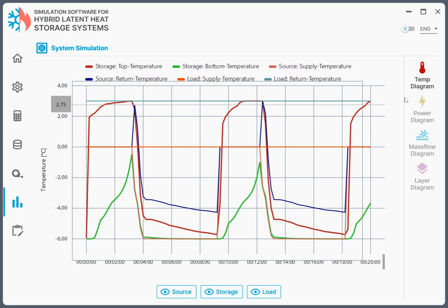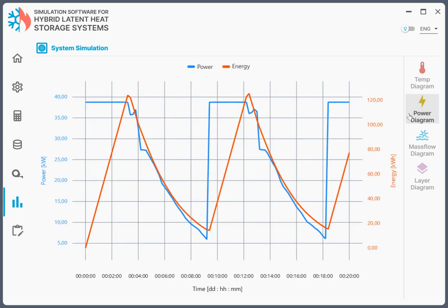You now see the behavior of the tank system and the chiller. Here we see how long the tank system is able to deliver close to 40 kilowatt. After 3.10 minutes the tank runs empty, must be regenerated, and after regenerating the tank system, we can deliver for the next time an amount of approximately 120 kilowatt hours cooling capacity to the system.